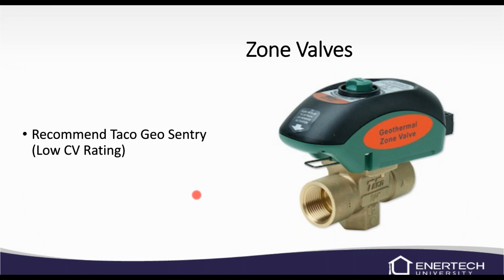This is the zone valves that we recommend here at Enertech. We use these quite a bit on open loops and on zoning systems. It's a Taco Geo Sentry valve. It's got a low CV rating. They're very reliable. It has an end switch that'll have a little light indicator to let you know when the valve is open.